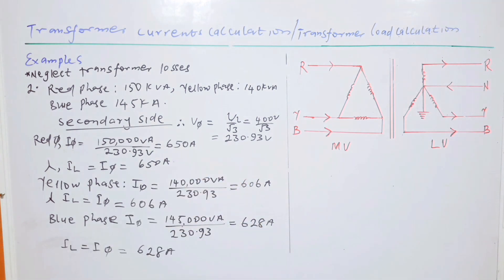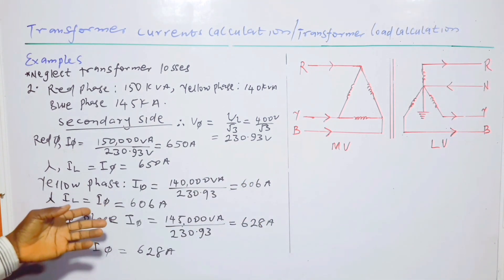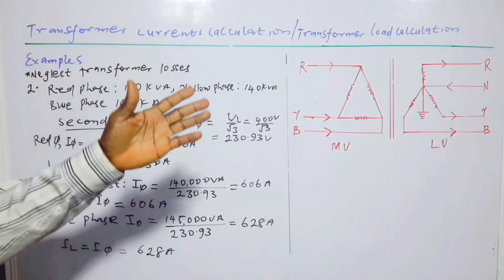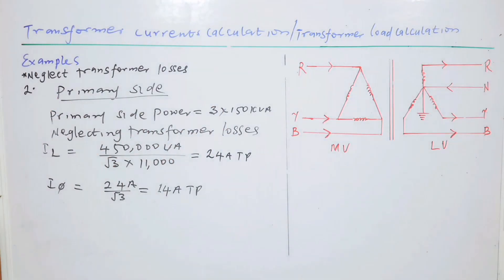Yellow phase: 140,000 VA / 230.93 V = 606 A, and the line current equals the phase current = 606 A. Blue phase: 145,000 VA / 230.93 V = 628 A, which is the same as the line current. For star connection the line current is always equal to the phase current.